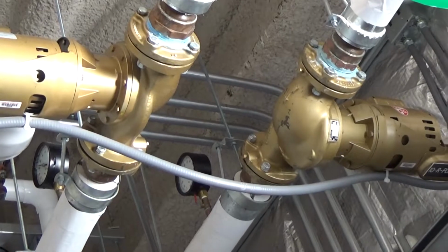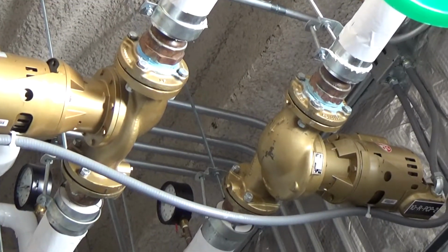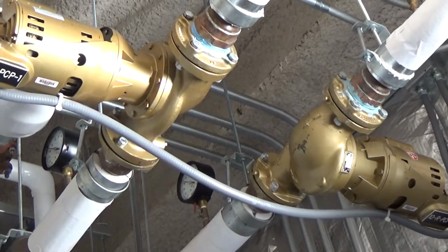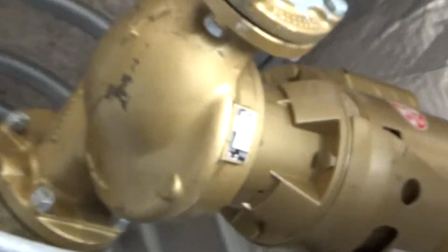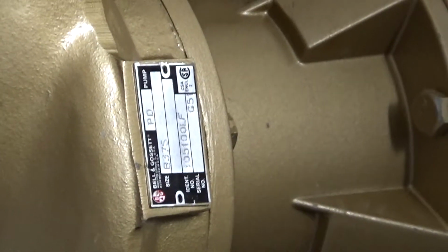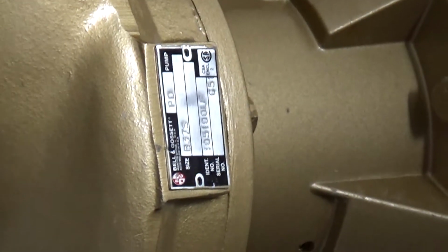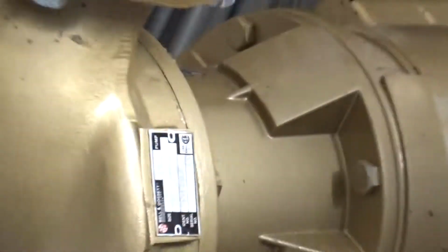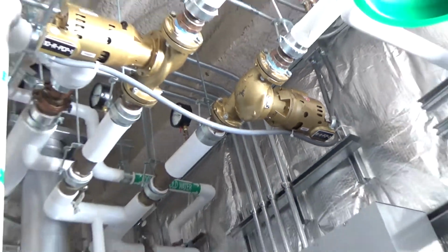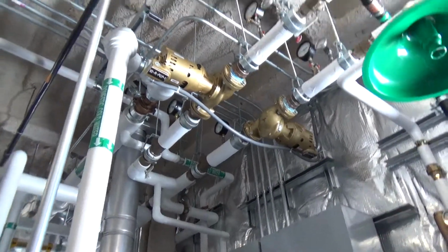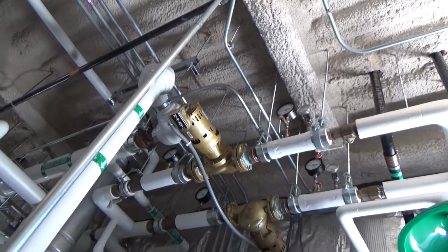And then the pump nameplate will give you the impeller size, the serial number, the model number, and all that kind of stuff. Always good for when you need to order parts. Grab that information, call who you need to call, and give them that info, and they'll get you whatever you guys need. Also, one thing I always suggest is to have your gauges on there. So get your differential right now, write it down.